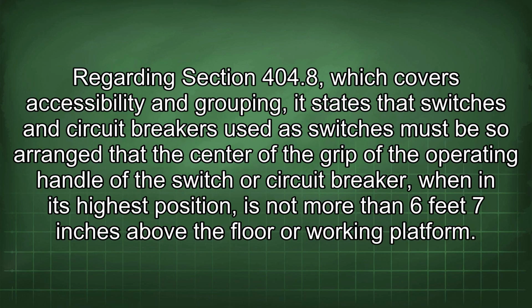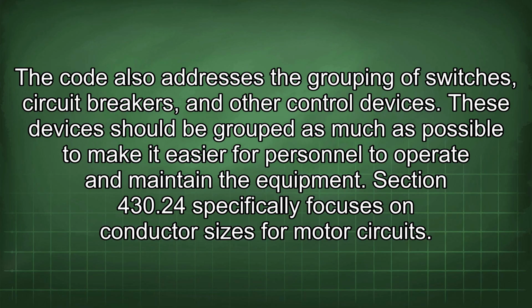Regarding Section 404.8, which covers accessibility and grouping, it states that switches and circuit breakers used as switches must be so arranged that the center of the grip of the operating handle of the switch or circuit breaker, when in its highest position, is not more than 6 feet 7 inches above the floor or working platform. The code also addresses the grouping of switches, circuit breakers, and other control devices. These devices should be grouped as much as possible to make it easier for personnel to operate and maintain the equipment.